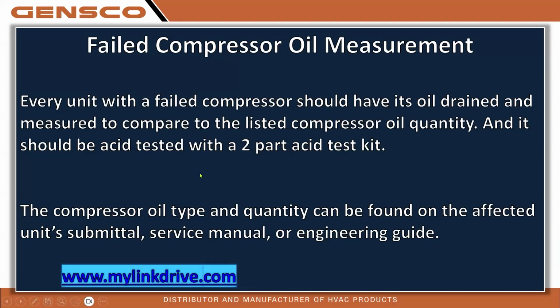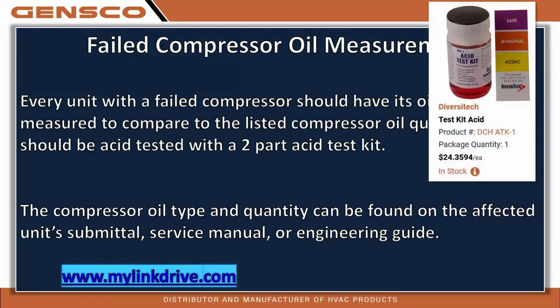So once you have decided to do that, okay, how much oil did I get out of the compressor? How do I know how much is in the compressor? One place where you can find that is either the unit submittal or service manual or the engineering guide. But be careful when you go here. And that is the only acid test kit you should ever be using, one that is two-part, not those little quick tests that you just stick on the Schrader core. Those are not accurate.